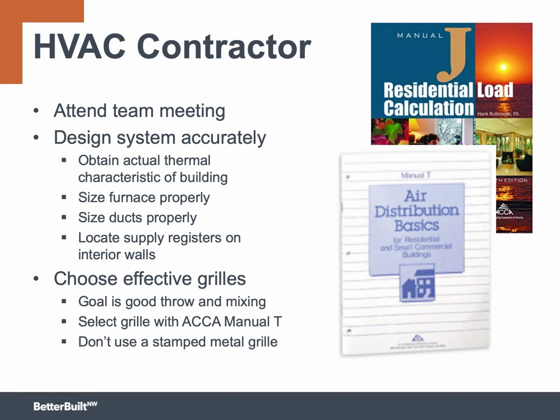They'll use Manual T to select the proper terminal for the supply registers. The goal is to get proper mixing and really get good throw out into the room. And very often that's not going to be the typical stamped metal grill that we're accustomed to seeing in homes these days. It's going to be something a little more sophisticated, maybe something that might more often be seen in a commercial building. It doesn't always have to be a more expensive grill, but they should at least go through the process of figuring out which product is going to work properly.